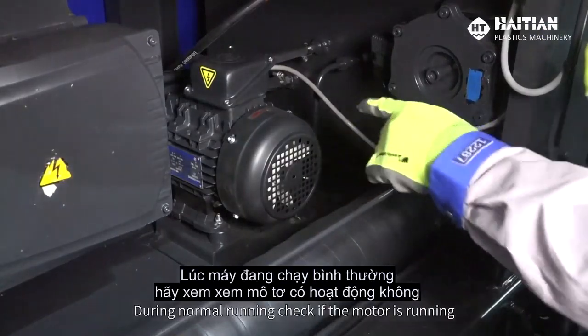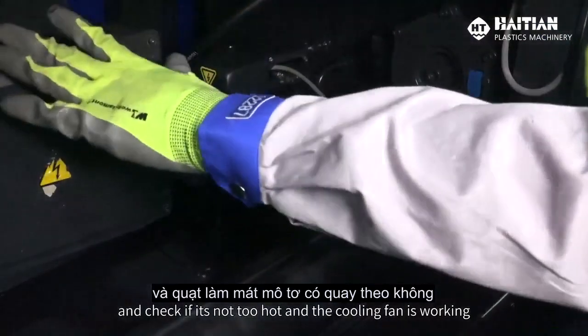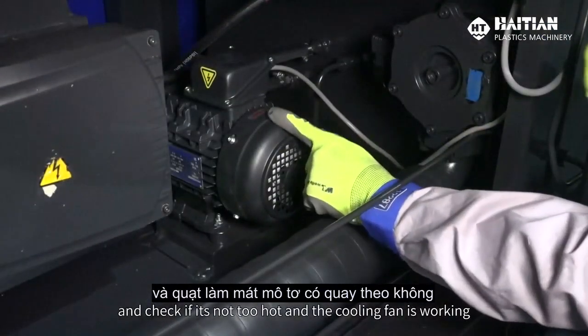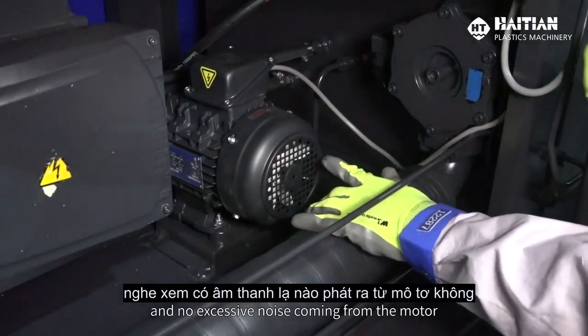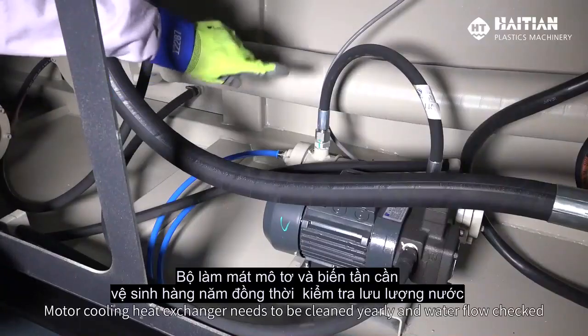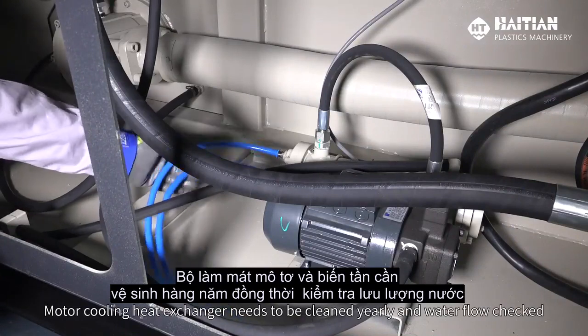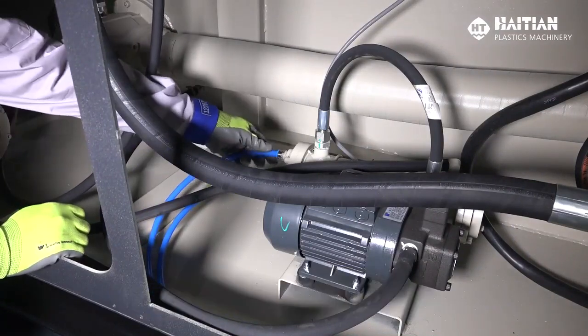During normal running, check if the motor is running and check that the motor is not too hot and the cooling fan is working and no excessive noise coming from the motor. Motor cooling heat exchanger needs to be cleaned yearly and the water flow needs to be checked.